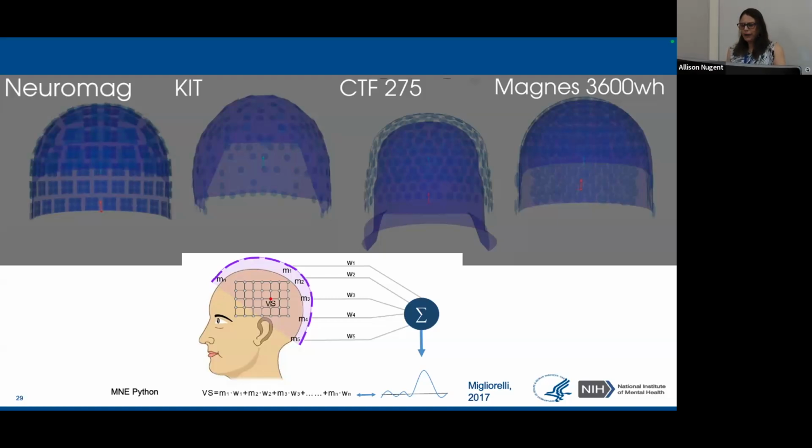On another note, how noise is compensated is quite a bit different across the vendors. Our machine, a CTF machine, uses an array of reference sensors above the primary sensors, and it uses those to synthesize higher order gradiometers that are really good at eliminating noise, but other vendors use purely software filtering methods. There are advantages and disadvantages to both of these methods.